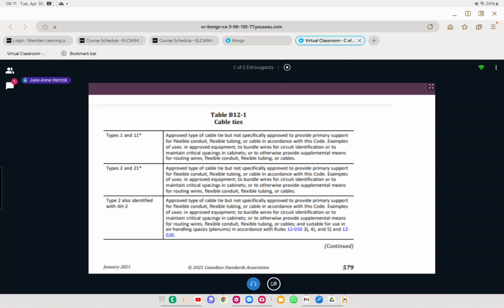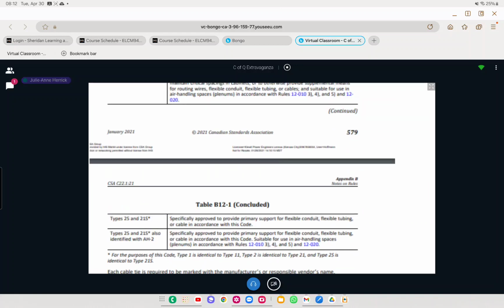A type 2 and 21 cable tie is approved as a type of cable tie, but not specifically approved to provide primary support for flexible conduit or flexible tubing. So if you get a question asking what kind of cable tie you use for flexible tubing, it's type 2 and 21.